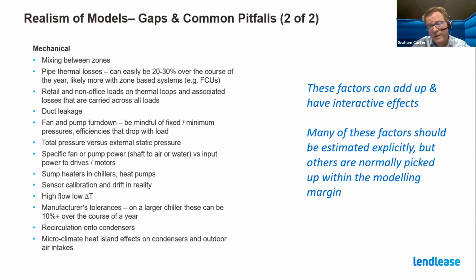Fan and pump turn down, we had a lot of really optimistic simulations that would assume these beautiful cubic curves in terms of how fans and pumps turn down. That's not reality. You've got fixed pressures, and efficiencies drop as you turn down. I think we're a lot better at that as an industry in Australia, if not globally, but historically it's been quite a challenge, as has the terminology around total pressure versus external static pressure, the difference being the losses that occur within the actual air handlers across coils and filters and things like that.